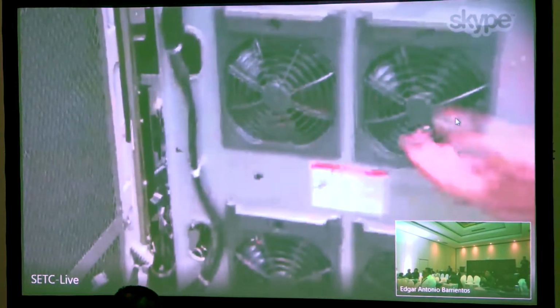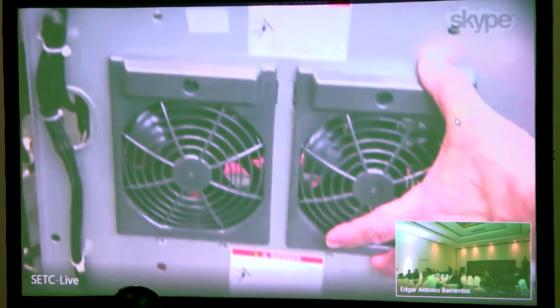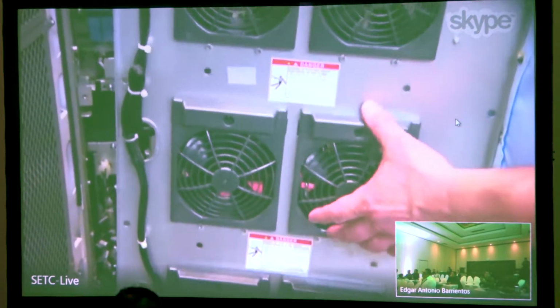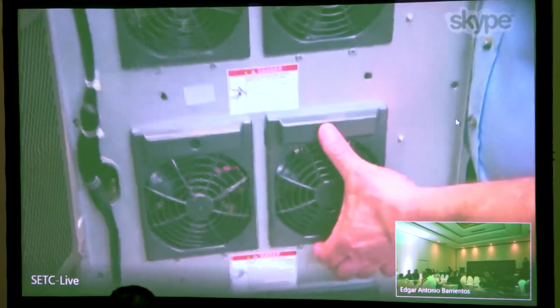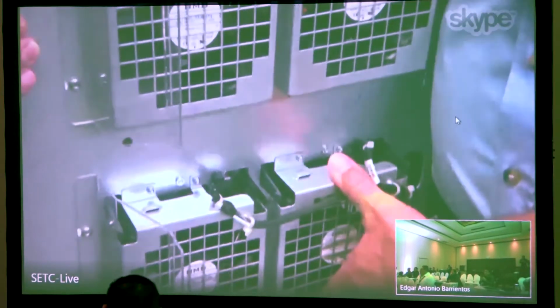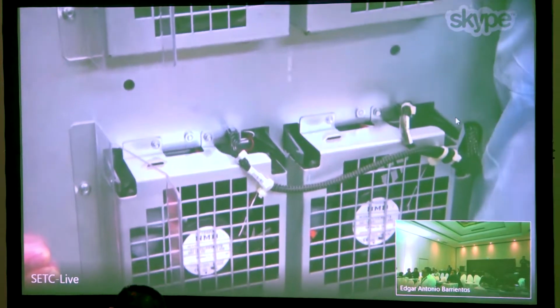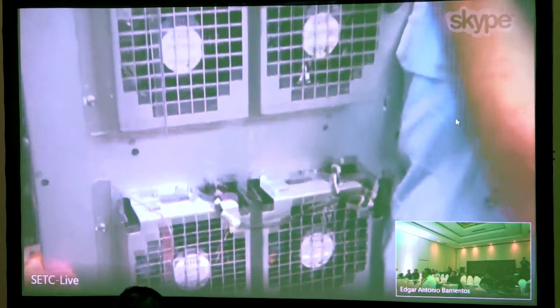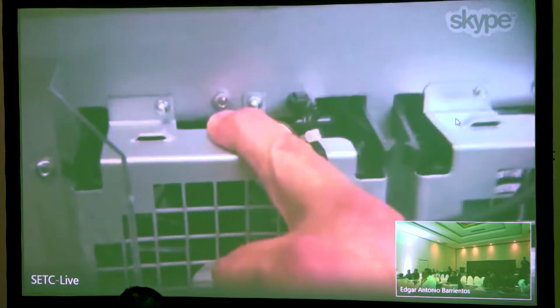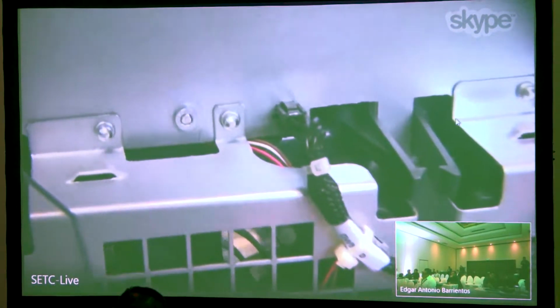What I really want to show you on the door are the fans. These fans are replaceable while the unit is running, and this static bypass switch can do 125% continuous with one fan gone. I'll show you removal and replacement of a fan on the UPS while it's energized with load, but note here that all the fans are encapsulated on the door, making them easy to access and replace while energized. We basically have a screw at the top, a Molex connector, and a couple of ears and tabs for retention.